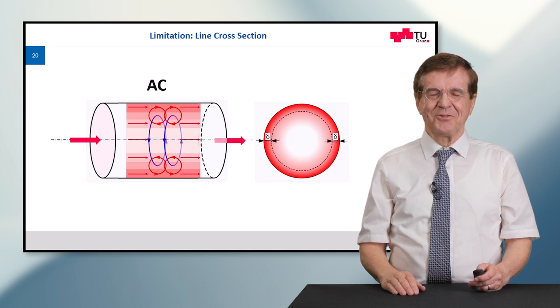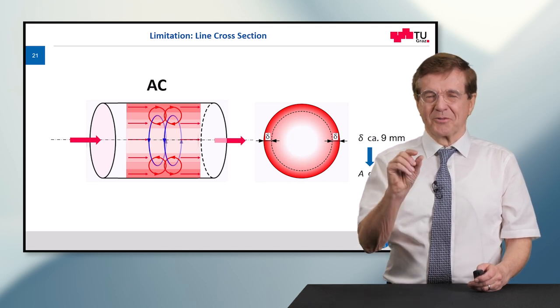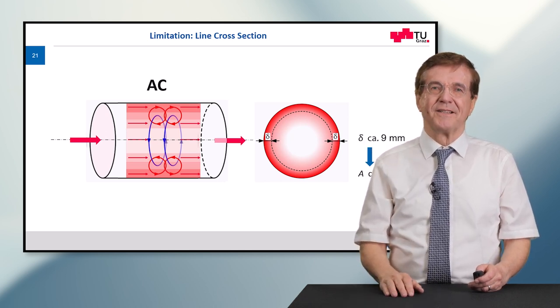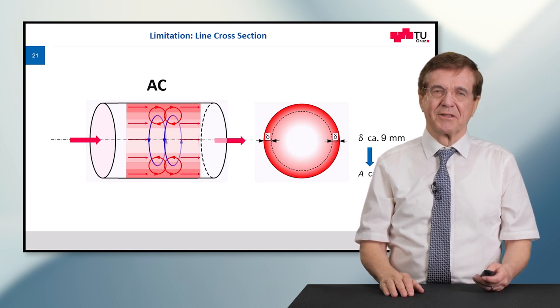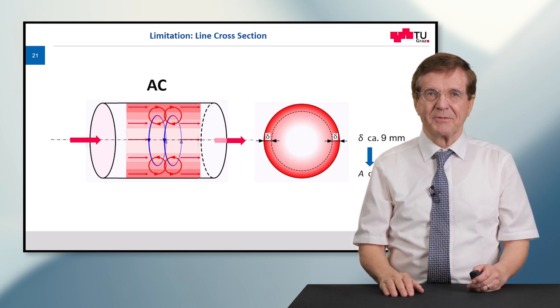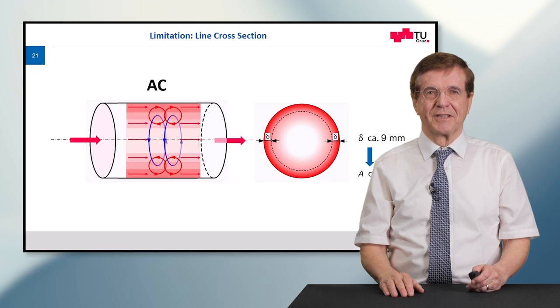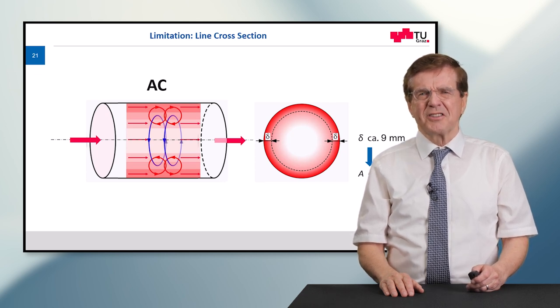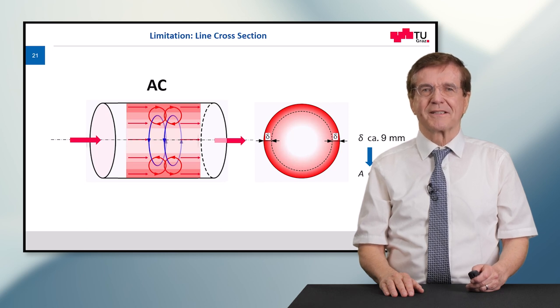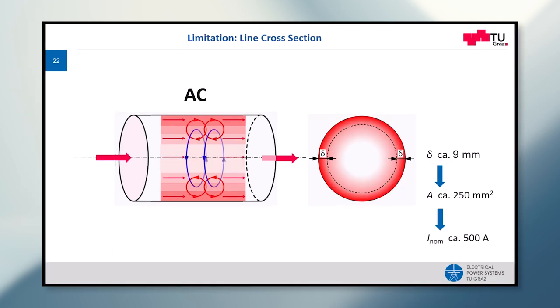Now calculations show that this so-called penetration depth is something like nine millimeters in material like copper or aluminum, which we engineers apply for the transport of electrical energy. And this generally means that only a surface of 250 square millimeters can be used. And in order not to get overheating on such a line, a typical line current under these circumstances results in 500 amps.